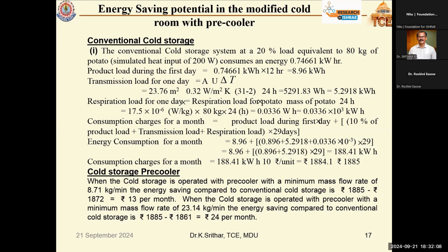So when 80 kg of potato is stored in a cold storage and run continuously for 30 days, the total load we have calculated is 188.41 kilowatt hours, and multiplied by the unit cost, the total electricity bill is 1,885.